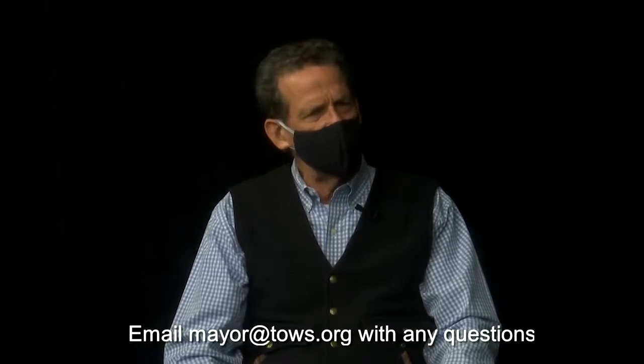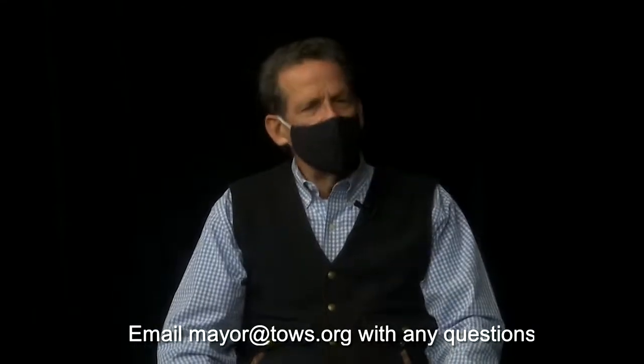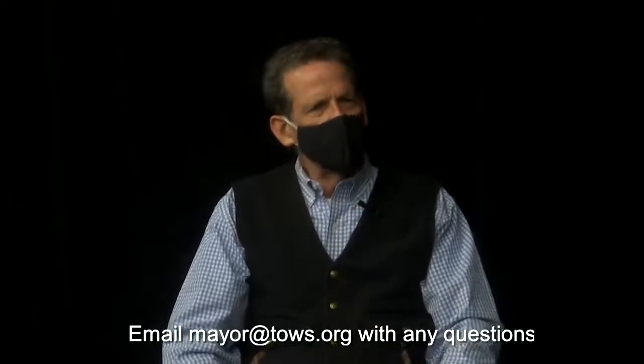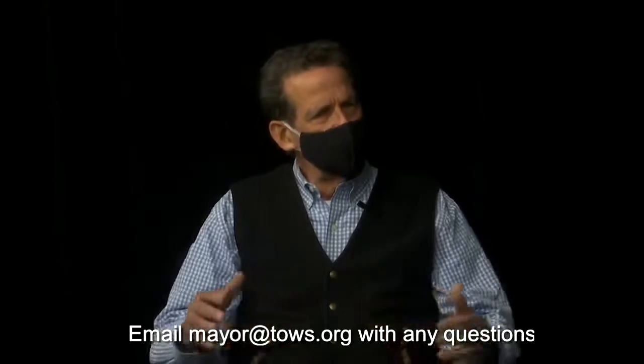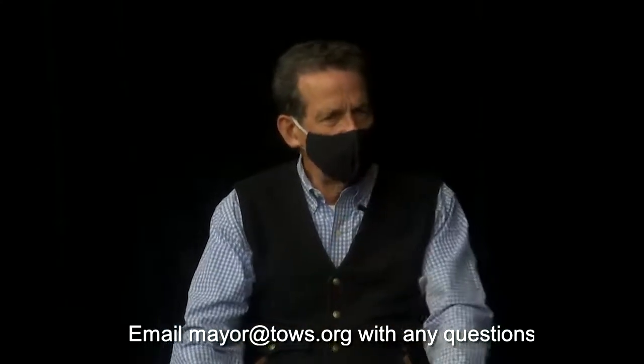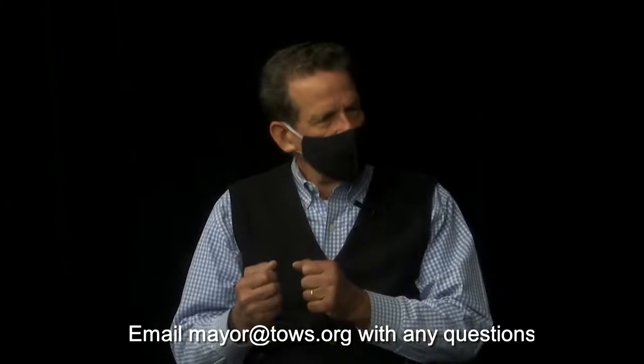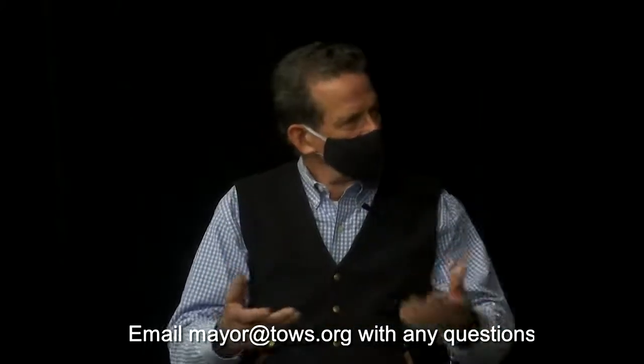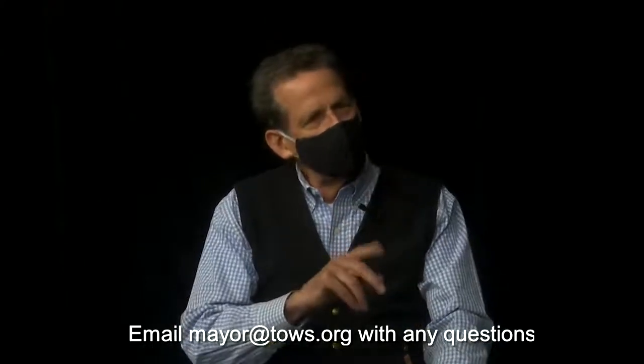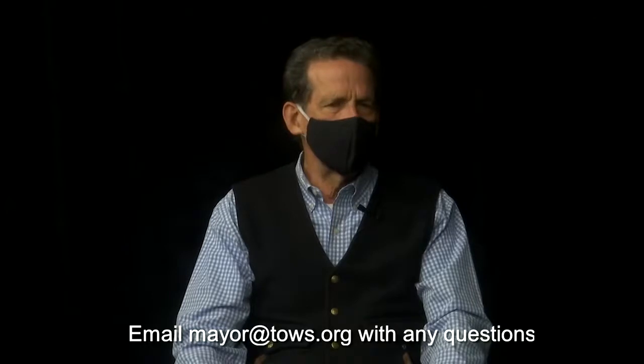There was a specified MERV rating, which is the rating for the filter type. We were looking to see what MERV ratings we had. The CFM tells us how often we can change the air in any area each minute or each hour. So what I did was calculate how much air was moving through the system and then the size of the room or space being serviced. From that, a calculation can be made for the air changes per hour — which is what the government was looking for in terms of a known rate of return.